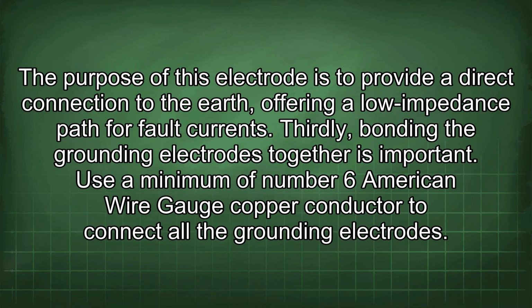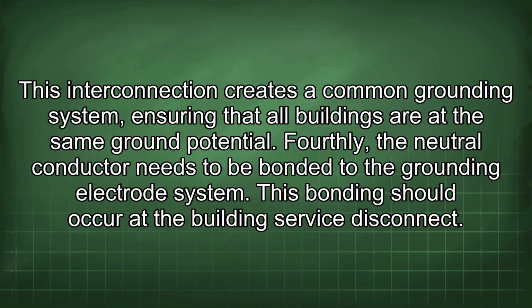The purpose of this electrode is to provide a direct connection to the earth, offering a low impedance path for fault currents. Thirdly, bonding the grounding electrodes together is important. Use a minimum of number 6 American wire gauge copper conductor to connect all the grounding electrodes. This interconnection creates a common grounding system, ensuring that all buildings are at the same ground potential.